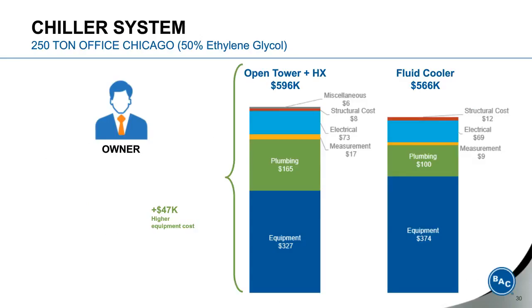So let's look at a deep dive on the 250-ton Chicago case for cooling an office building. We have on the right-hand side of the screen the fluid cooler, and on the left the open tower heat exchanger. And the first thing you really notice is that the equipment cost for the fluid cooler is $47,000 higher than the cost of the open tower heat exchanger equipment. And that's including freight and everything like that. And a lot of times folks will just look at that equipment cost and not go any further.